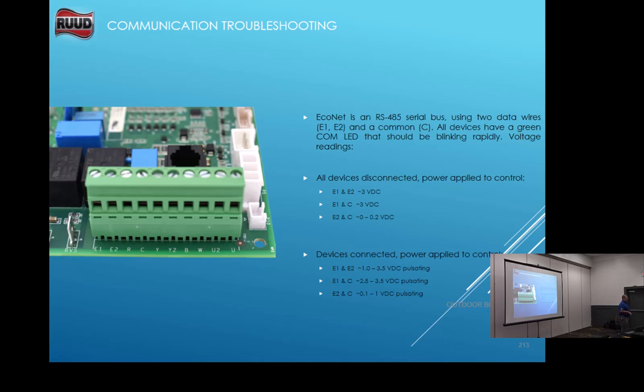So if I tell you, okay, you need to go through and check all your wiring, Mike, I already have. This is what checking all of your wiring includes. It means going in, taking your screwdriver, unscrewing this E1 wire, pulling the wire out and looking at it and going, okay, I got it stripped back, there's no insulation under there, and putting it back, and doing every one like that, okay? It means going to the thermostat, pulling that controller off of the wall, and checking all of those wires in behind the connection to make sure that insulation is stripped back from the wire.